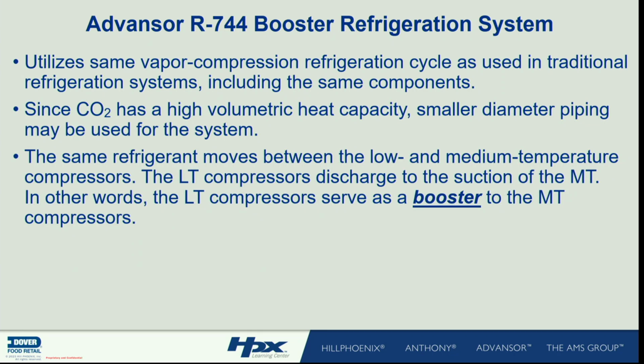What do I mean by booster? I'm talking about 2 sets of compression using 1 refrigerant. Two sets of compression, medium and low, 1 refrigerant passing between the 2, discharging the low temp compressor into the medium temp. Anybody ever work on a Carlyle 2-stage back in the day? R22 low temp, is that a booster? I'm taking 1 set of compression, I have an interstage to the other set, compressing on the interstage, reducing my compression ratio, allowing me to go low temp R22 to ambient without too much heat built into the compressor, amen? I'm basically doing the same thing here, it's nothing new. This is not hard, nothing new, so just keep that in mind.